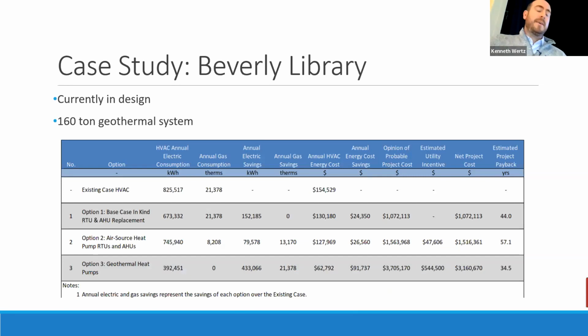Beverly Library, they're going geothermal. So we did a study for them to look at different technologies to give them some options of which way they wanted to go. So we looked at just replacing their existing rooftop units and air handlers and keeping the boilers. And that was going to get them about $24,000 in savings. They could go with the air source heat pumps instead of the boilers, and that would get them a little bit more savings. That'd be $26,000.